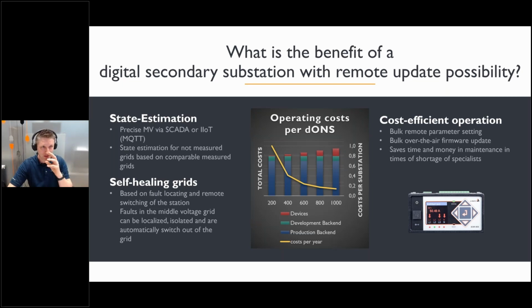There are three main topics that you can tell. First one, state estimation. You want to have precise middle voltage measurement values via SCADA and IoT for asset management as well as for the central SCADA system. And you want to have these data for state estimation of not measured grids based on comparable measured grids. So the task is not to equip 100% of all digital secondary substations in such a digital manner, but only to equip 10 to 20% to do state estimation for the rest of the network. This is the first big topic.